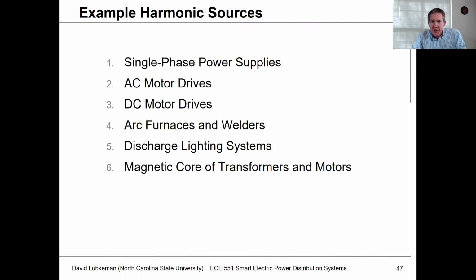So as far as the different types of harmonic sources that we would typically be seeing, these would be at customer loads. And you would have single phase power supplies. There's a lot of these, but they're not really that large, but they would have an additive effect. You have AC motor drives, DC motor drives. Arc furnaces and welders, if you have those at the distribution level, would have a very high harmonic content. And then you would have maybe some special purpose lighting systems like some discharge lighting systems.